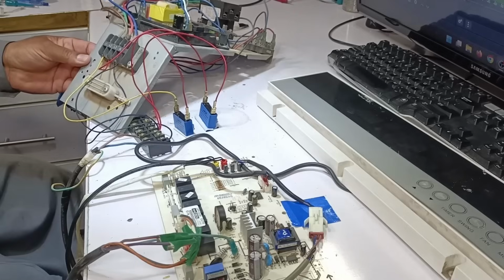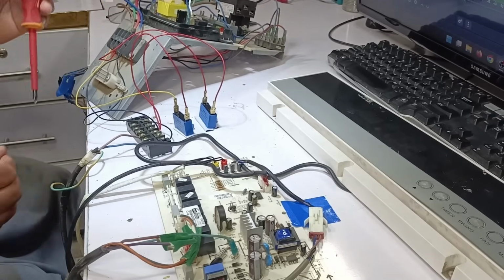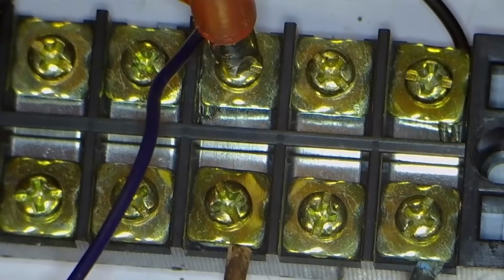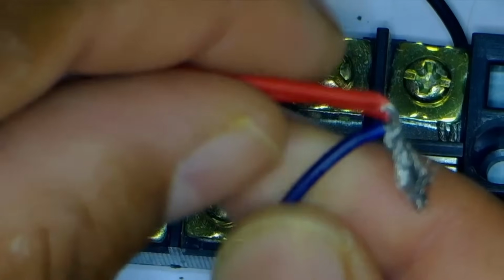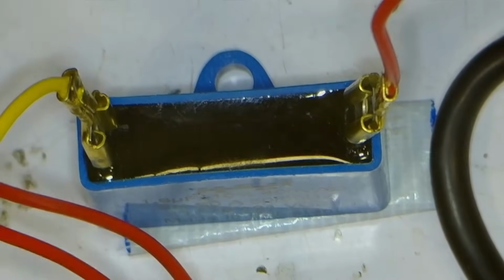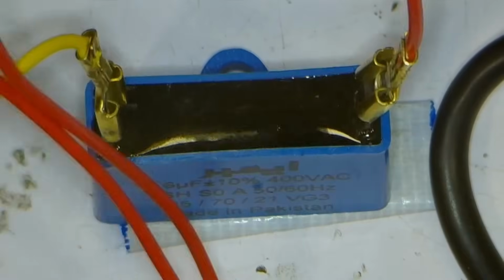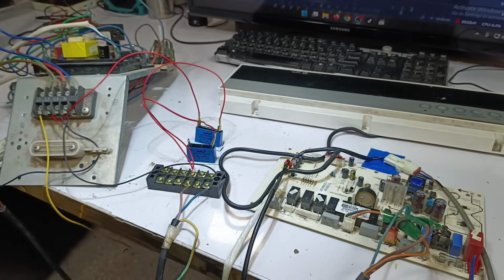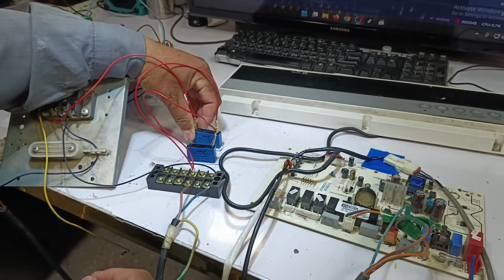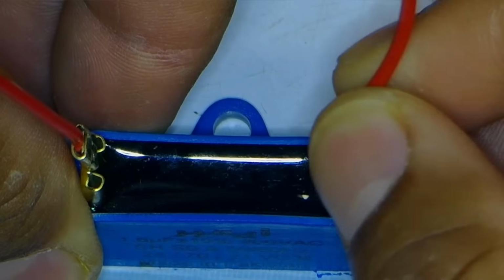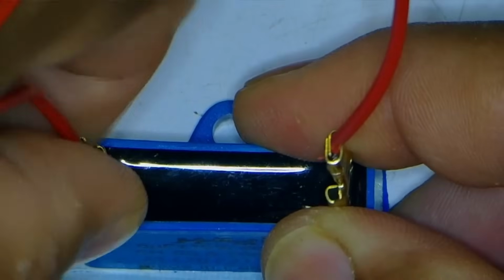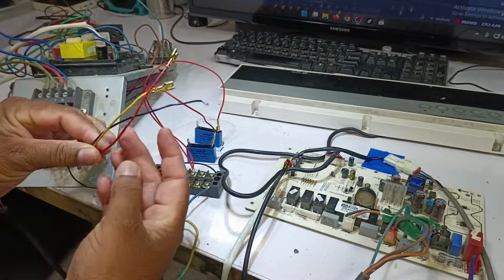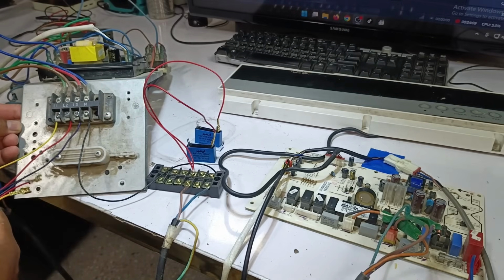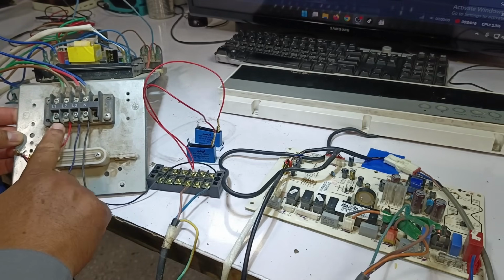For this, we will first remove all the line connections, leaving only the neutral connection in place. The supply that we were providing to the circuit board will also be disconnected. The wires coming from the capacitors will be reattached temporarily, but the wire that was carrying the main supply from the capacitor to the circuit board will be disconnected. One red wire, which is from the main supply, and one yellow wire, which was connected through a capacitor, will both be disconnected. In the second capacitor as well, there are 2 red wires. The wire that is receiving the phase, live power, will remain connected, but the wire going toward the circuit board, output, will be disconnected. In this way, we have removed all the phase wires from L1, L2, and L3.